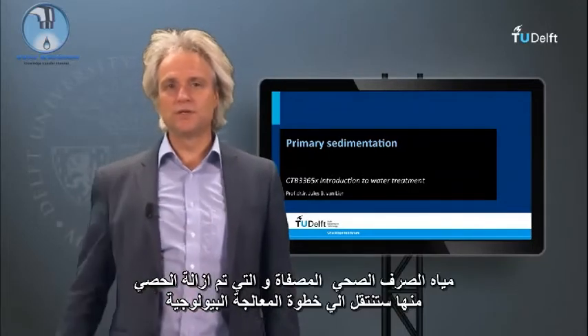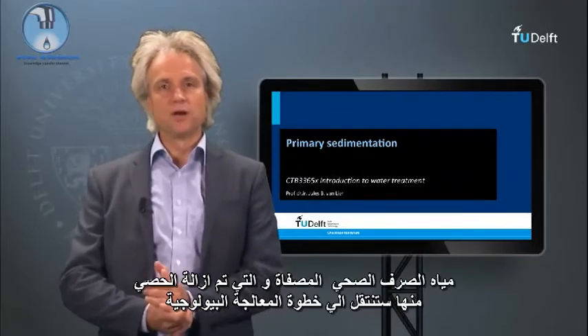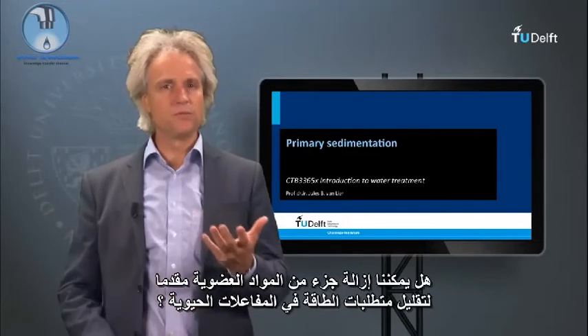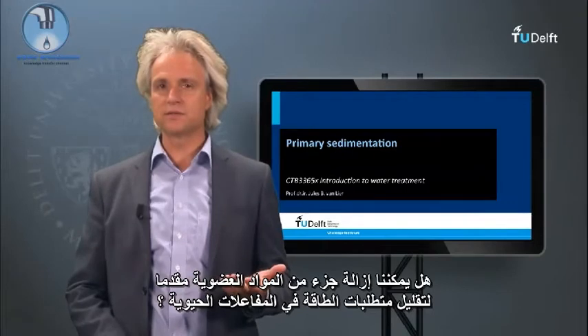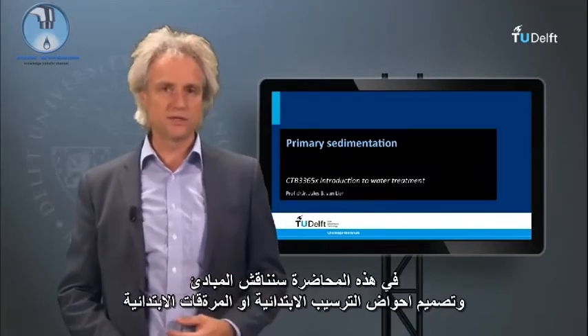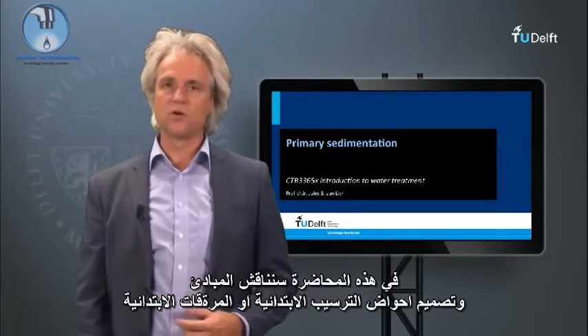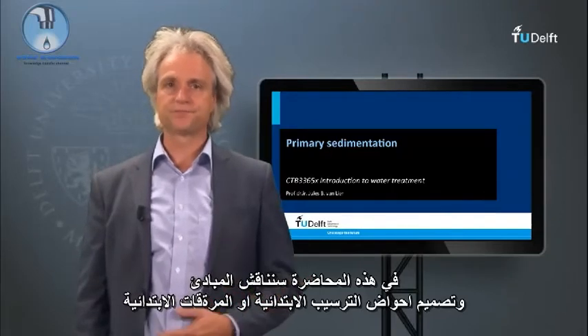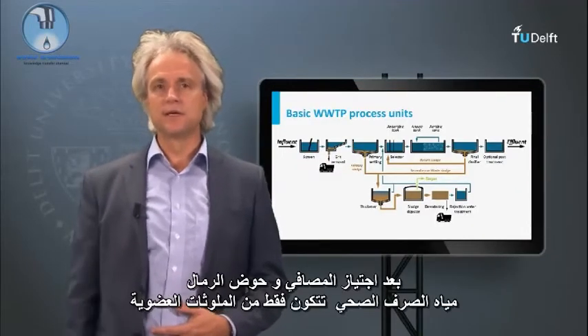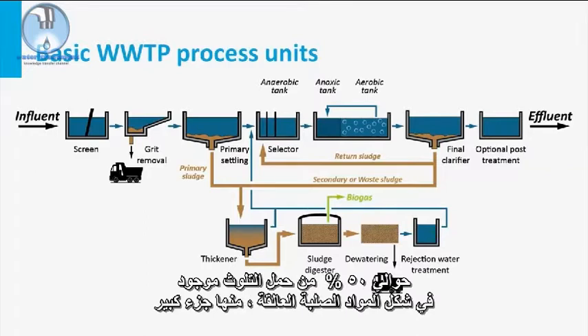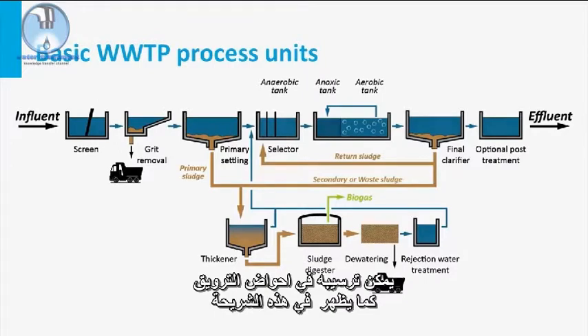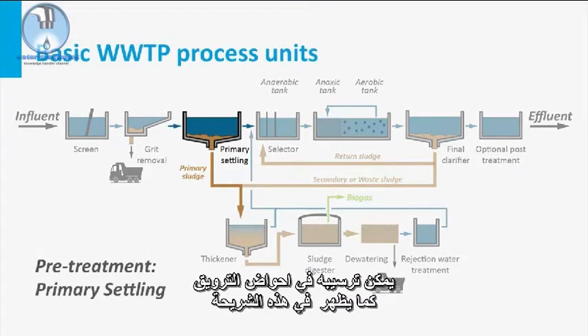The screened and de-gritted sewage is further conveyed towards the biological treatment step. Can we remove some part of the organic matter upfront to minimize energy requirements in the bioreactors? In this lecture we will discuss the principles and design of the primary settlers or primary clarifiers. After passing the screens and grit chamber, the sewage merely consists of organic pollutants. About 50% of the pollution load is present as suspended solids, of which a large part is settleable in a clarification tank as indicated in this slide.